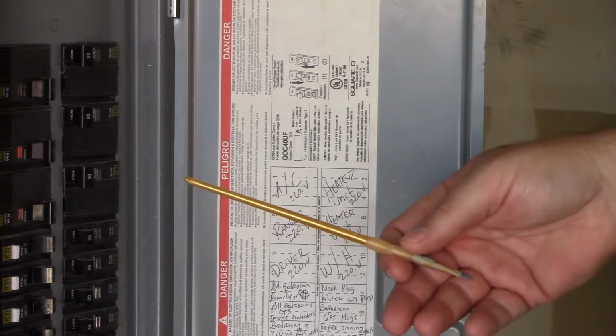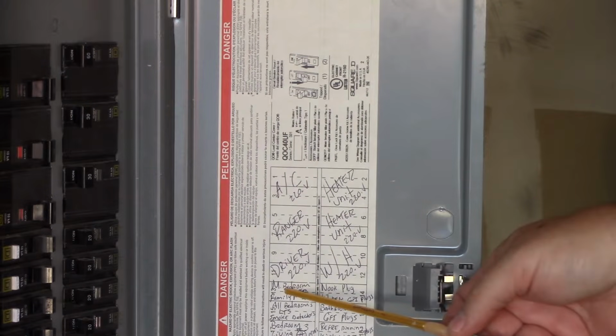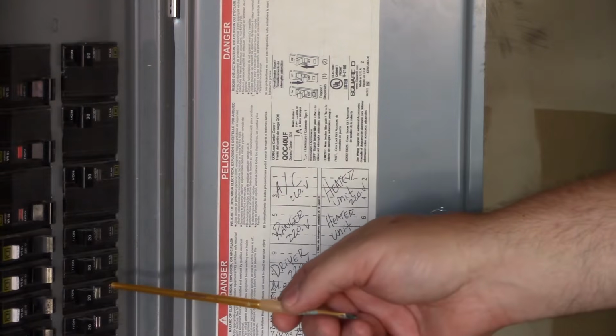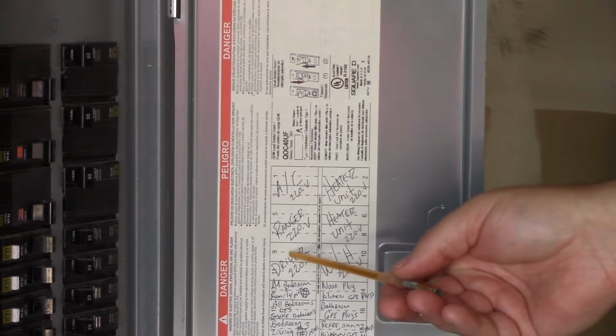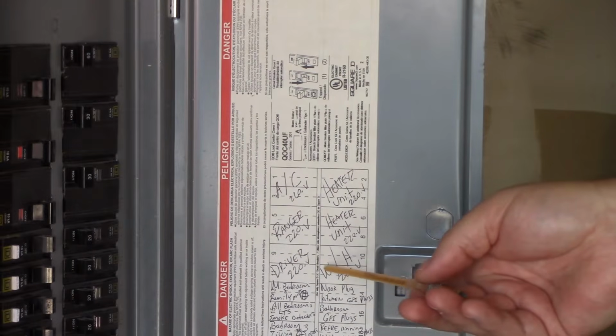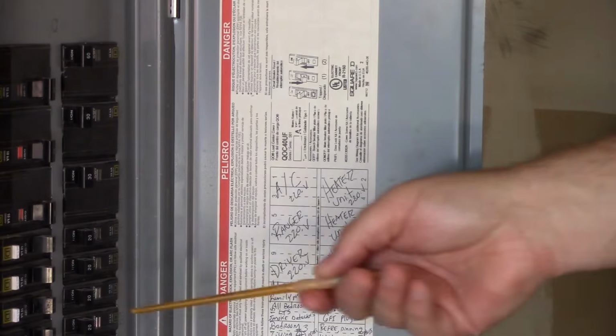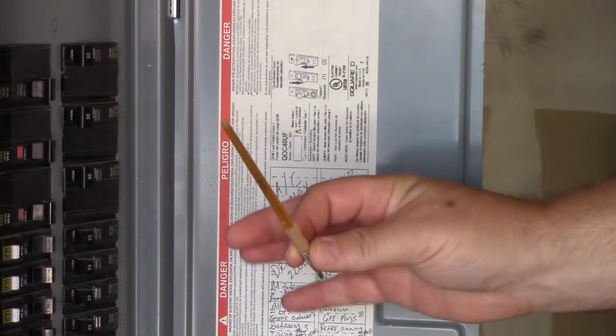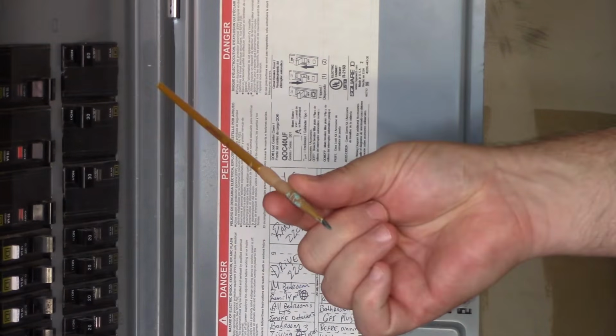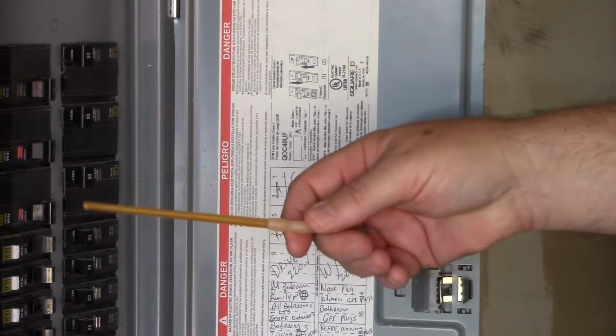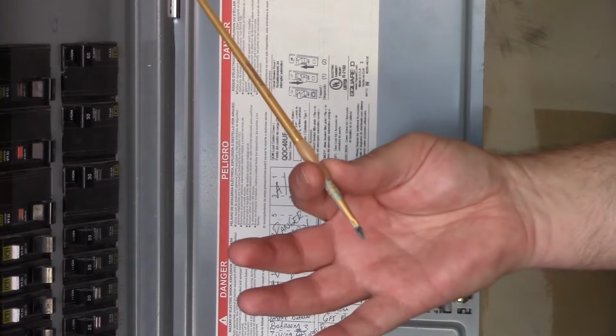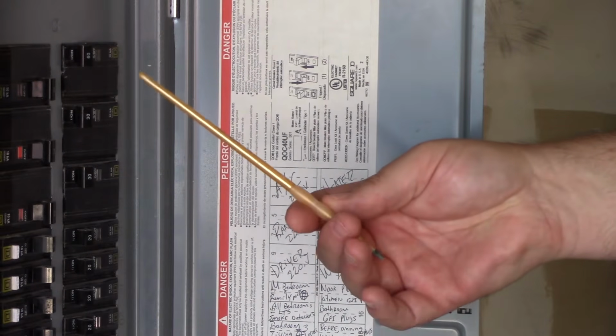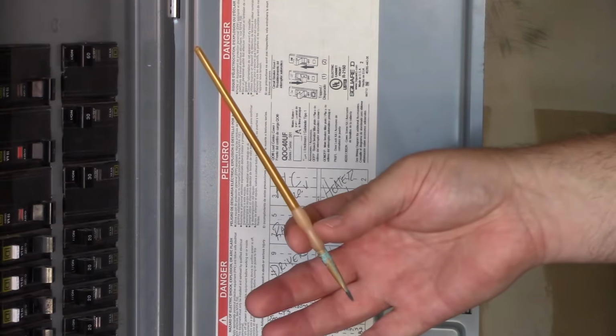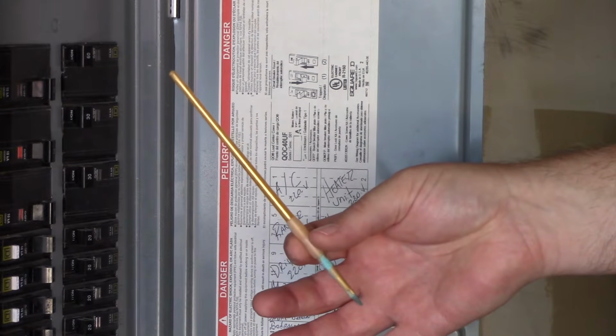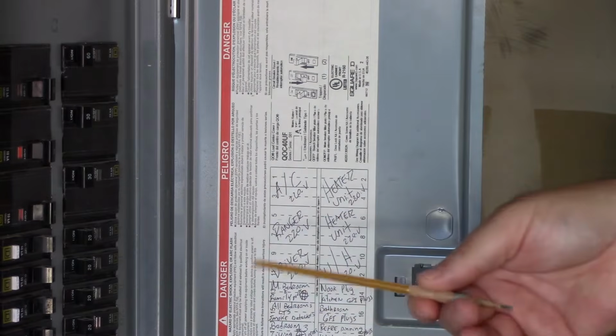All of this process, we're still trying to determine the size of this service, and we haven't really got there yet. We haven't even pulled the panel cover off. But we're looking down here now. If I see any breaker over here that's not reflected over here, then I'm going to call that out. If I have something that's missing, the directory's not filled out for a specific breaker over here, I'm going to call that out. Again, I will point out that I'm using a non-conductive probe. In my case, I like to use paintbrushes. I have different sizes depending on the size of service so I can get in there. But it's a non-conductive probe. It's not metal. It's plastic, and sometimes they're fiberglass, and sometimes they're even just a plastic material, or wood.